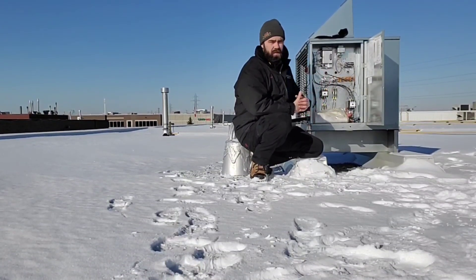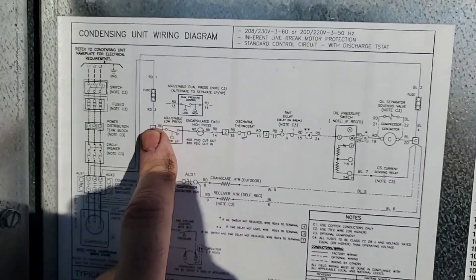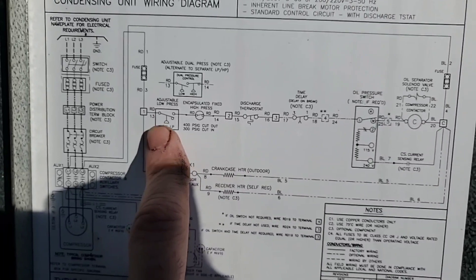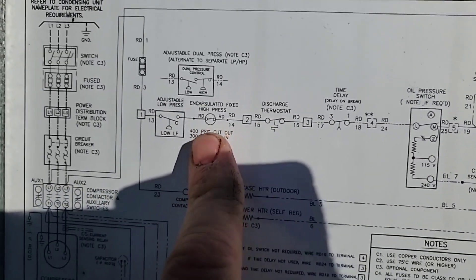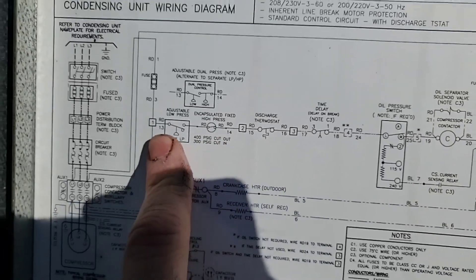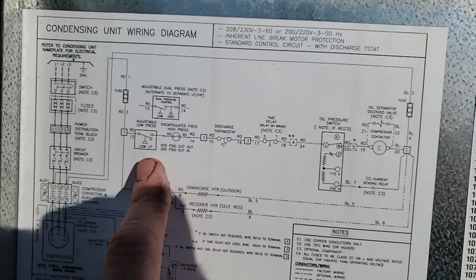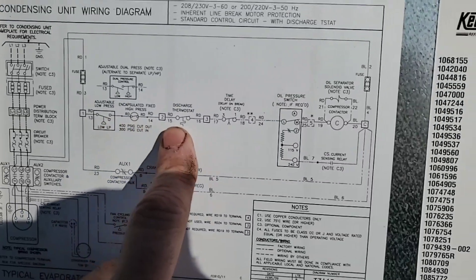This machine actually just started running as I was explaining this. On the diagram here, the first safety switch we hit is the low pressure switch — you can see how it's shown open. It also shows an encapsulated high pressure switch that is normally closed. This low pressure switch will close once the solenoid opens and the suction side of the system receives pressure. Then we come across and eventually get to the compressor contactor where it starts the operation.